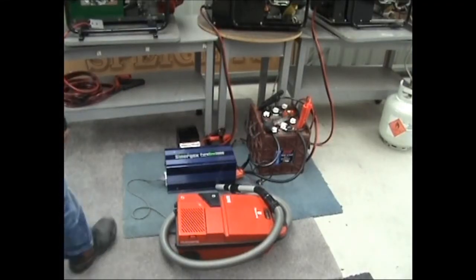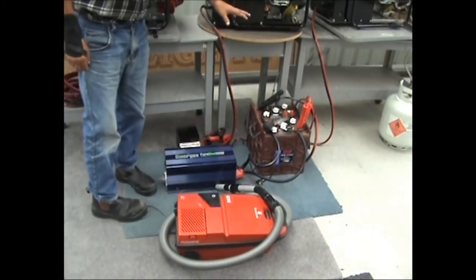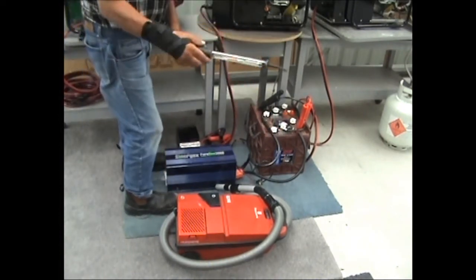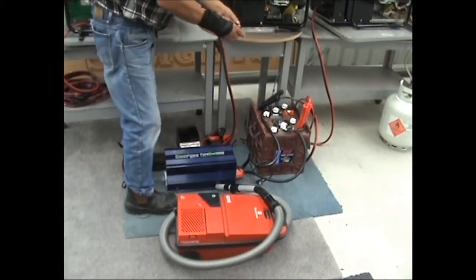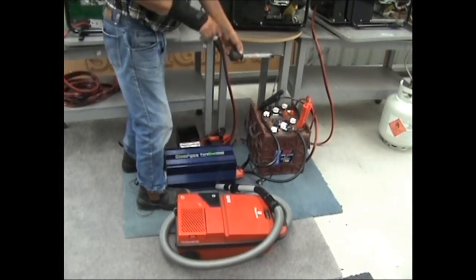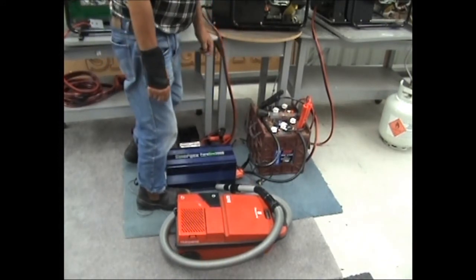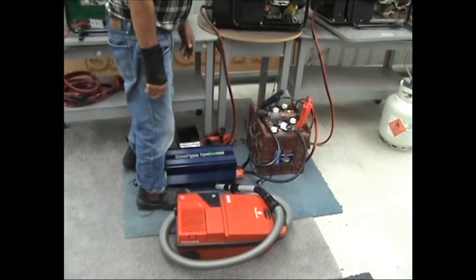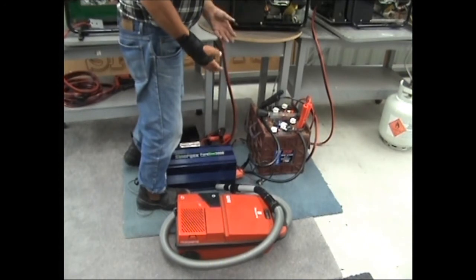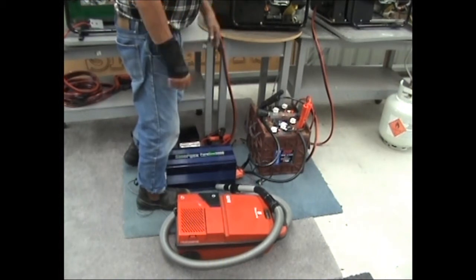Now because we're right into solar, it starts off at the battery, and you'll see there's a hydrometer. Still the most effective way of checking your batteries, and I personally like batteries that have tops so I can test them and look after them. If the battery is sealed, in my personal opinion, it is throwaway because we can't service it. For some reason the charger could have got too much, or something's gone wrong, and with sealed batteries you might as well throw them all away.